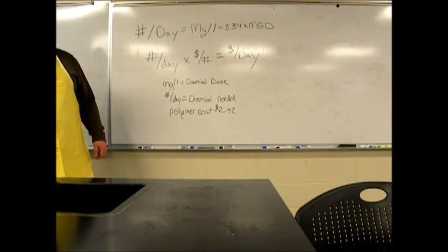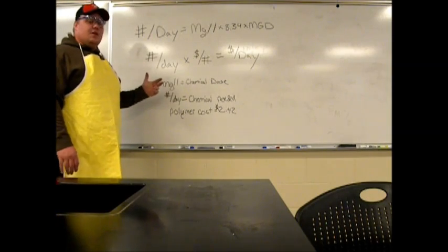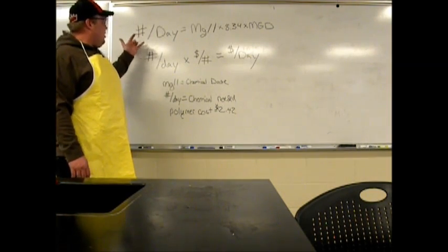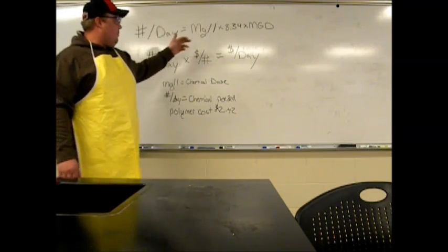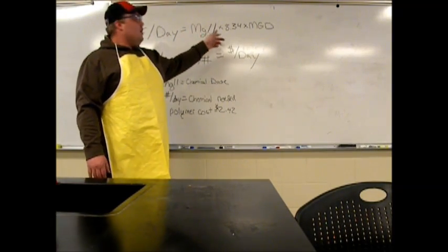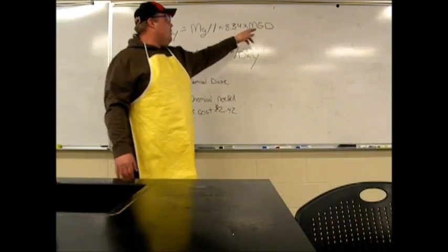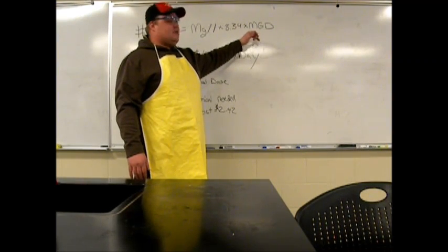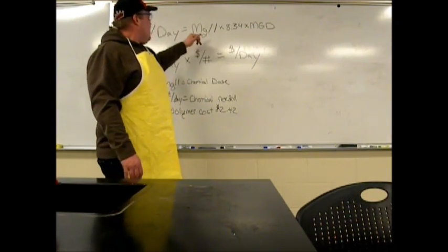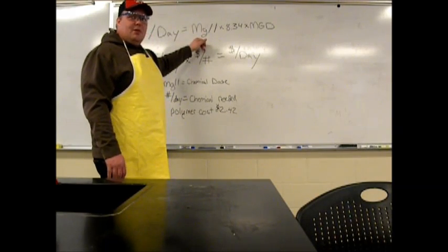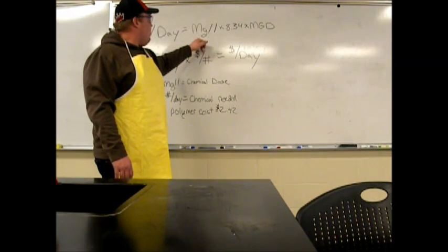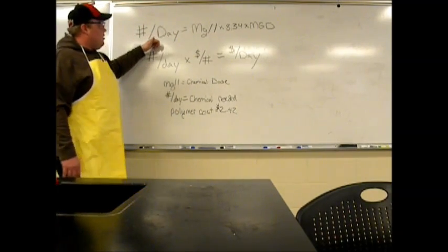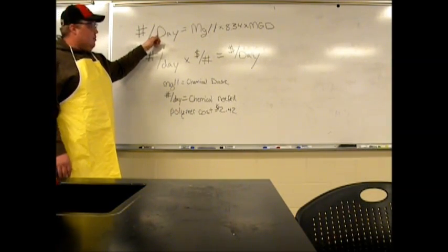Here are a couple of formulas that we use to figure out how much polymer you will need on a large scale. You have to figure out your pounds needed per day — you take your milligrams per liter, multiply by 8.34, and then by your million gallons per day. So you figure out how much water is coming through your facility, take your optimal amount of polymer or other coagulant, multiply them all together, and that will give you your pounds needed per day of total polymer.